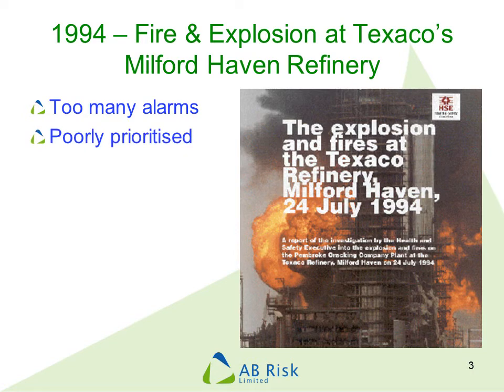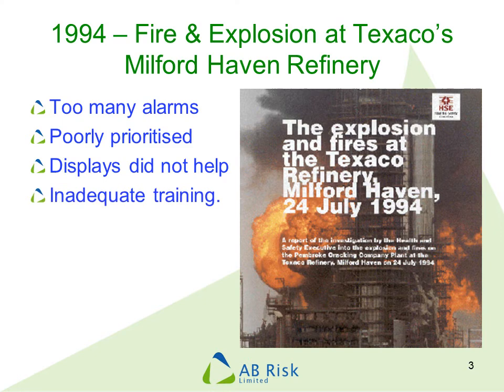The alarms received were poorly prioritised, so the operator could not decide which ones were important. The graphical displays provided were not effective, meaning they did not realise what was going on, and the operators had not been trained in how to deal with alarms or incidents. This accident report has informed a lot of guidance about alarms currently in use, though it is worth noting the accident occurred more than 20 years ago, but the same problems persist.